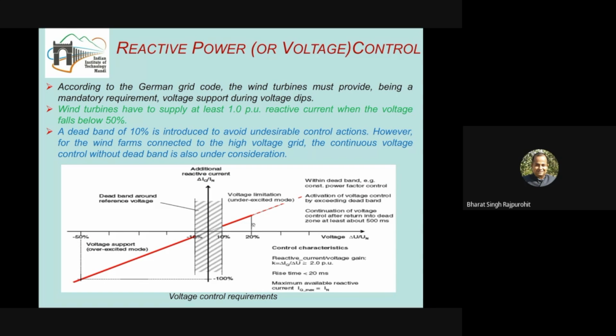Now see this curve. This curve is from a German grid code, which specifies how much reactive power should be provided to the grid when it is required. This curve is for a voltage sag condition. When the voltage is reduced, for example in the left-hand side figure, by 50% at the point of common coupling, then the amount of reactive power required from the wind farm or solar farm is around 100%, or 1 per unit. It means it is similar to the rating of the wind farm.